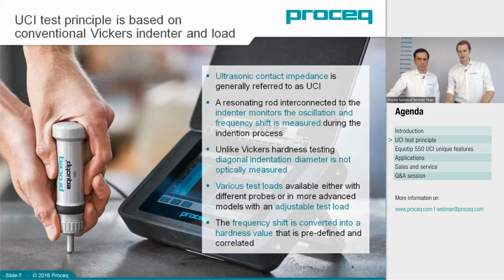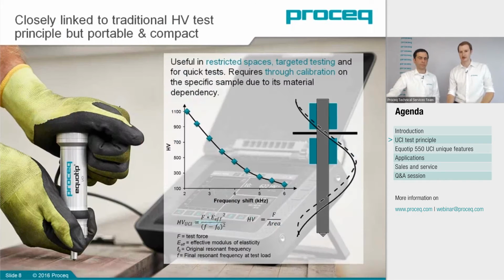Once the frequency shift is measured during the measurement, it has to be converted into a hardness value. This can be done with a conversion curve, which you can see here on the chart in the middle of the slide. That's an example of such a conversion curve.